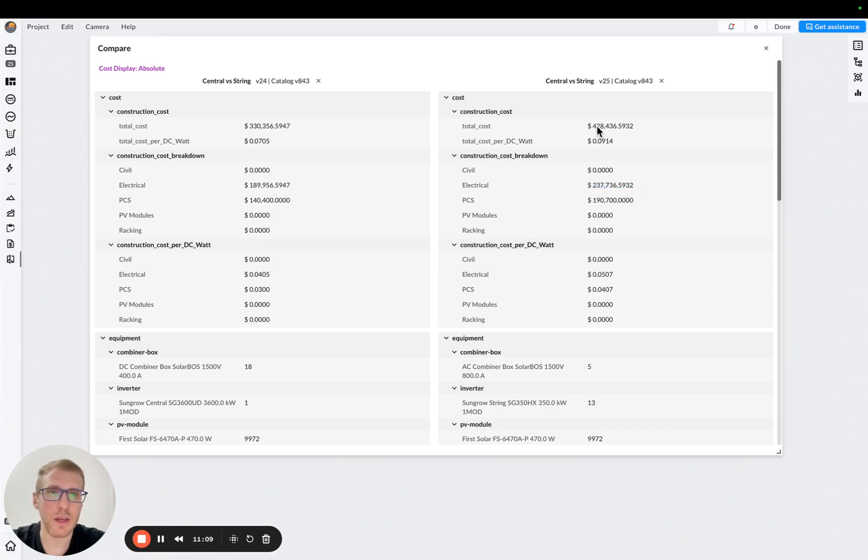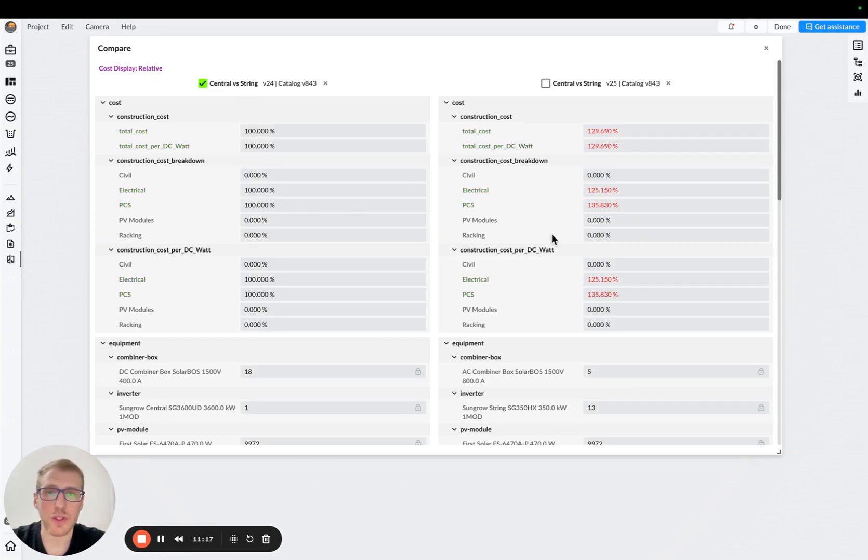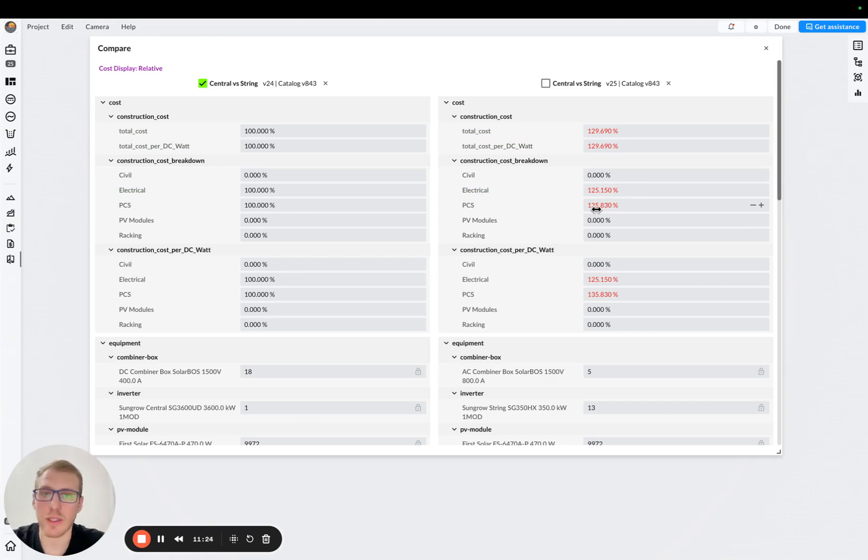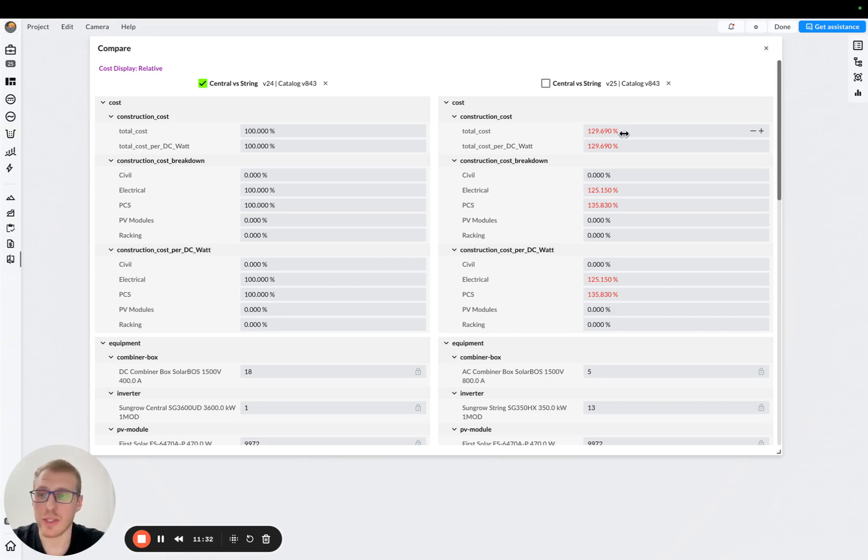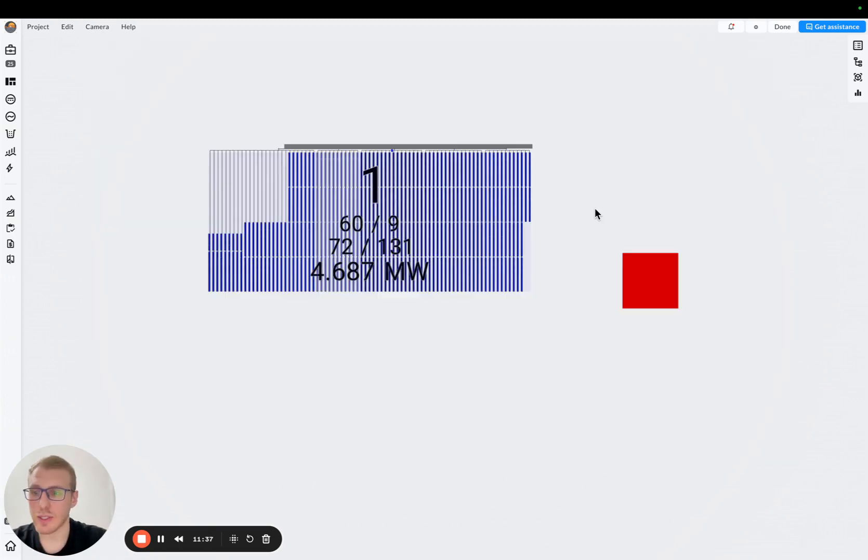So we can press on this, and we can see that our central inverter, our string inverter in this particular case is more expensive, 25% more expensive from electrical standpoint, and 35% more expensive from a PCS standpoint. And you can see here that the total cost is, basically 30% more expensive for the string inverter.